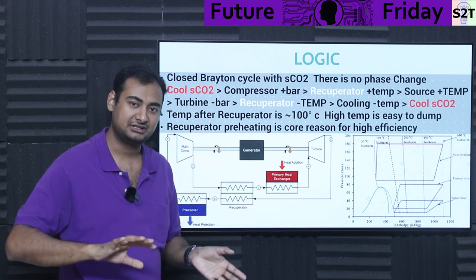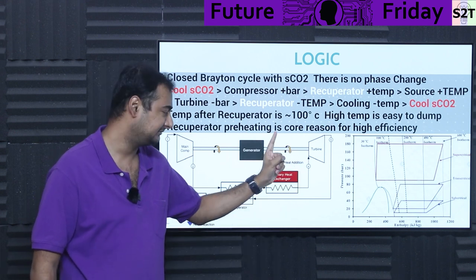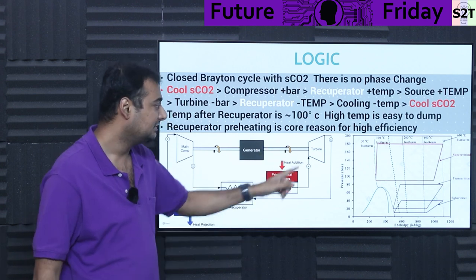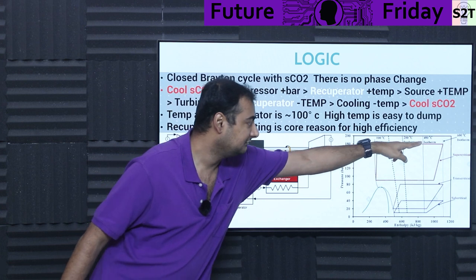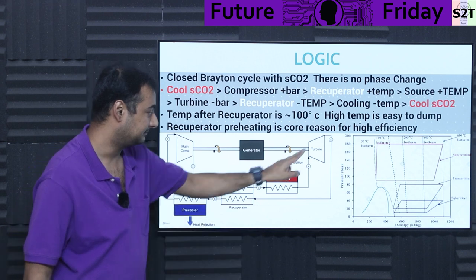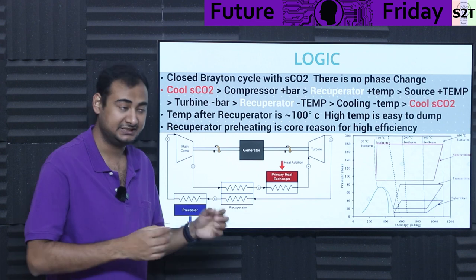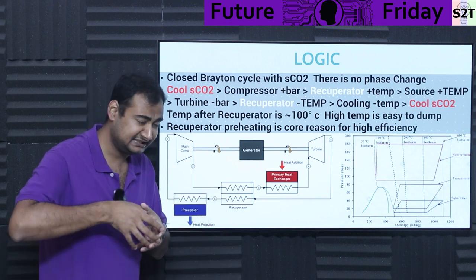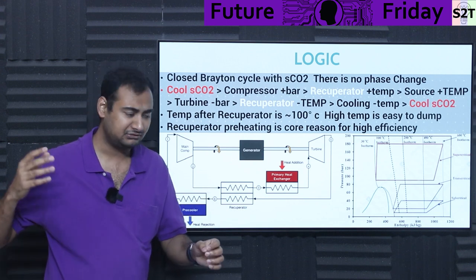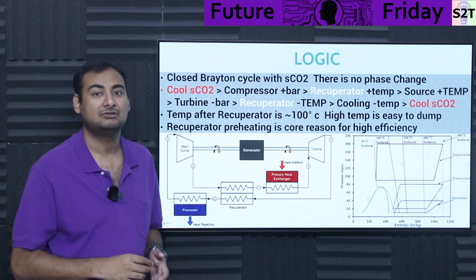Now the turbine can also be inverted and called an expander, because you send very high pressure, very high temperature fluid there, and the turbine turns and extracts energy out of it, so pressure drops. So at point 5, basically the output point, your pressure will drop from whatever the higher pressure was, back toward the main compressor. Now that pressure dropped a lot, however the temperature did not drop a lot. The same way in a steam turbine, you can send very high pressure steam, hundreds of psi, and the output could be literally a partial vacuum, but your temperature would not drop that much.